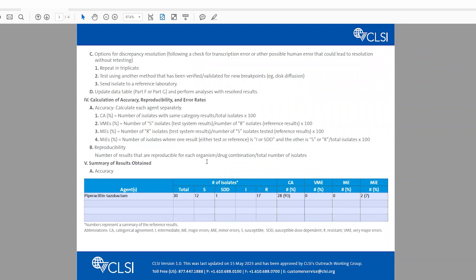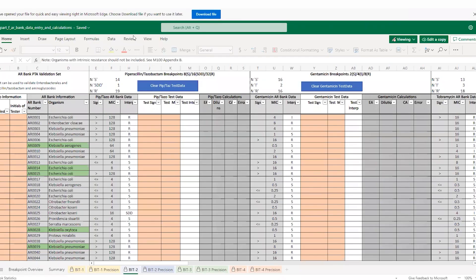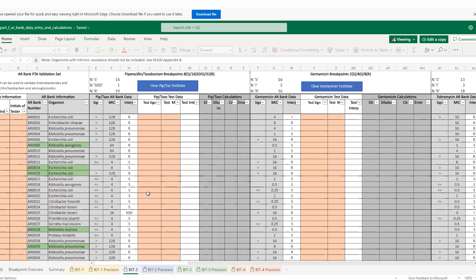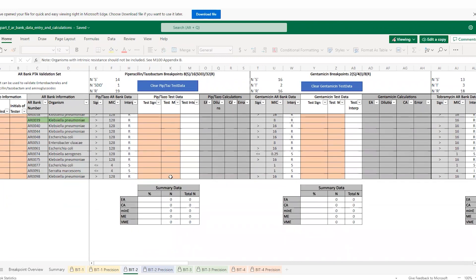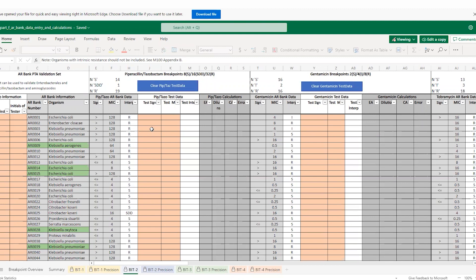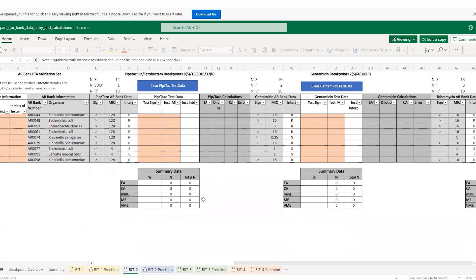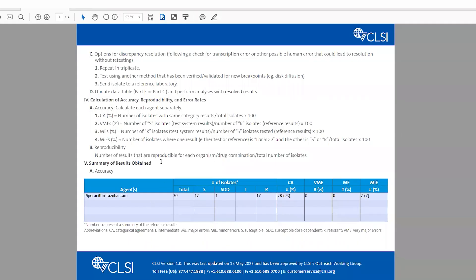Once you've outlined your verification or validation study using the first half of this document, you'll go about and do those studies as outlined. Then you'll come back to your summary at the completion of your verification and validation, utilizing the pre-filled Excel spreadsheet as Part F of the BIT, which will pre-populate results. You enter your values for the test under validation or verification, and it will pre-fill your essential agreement, categorical agreement, and categorical errors based on the data in comparison to the CDC ARBank reference results. You then take that information and plug it into your verification or validation summary in the accuracy table.